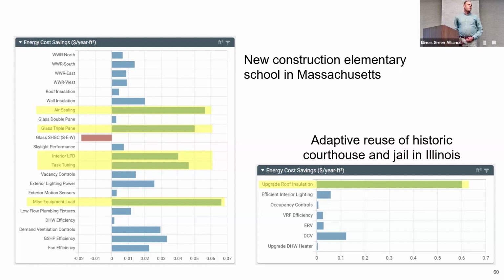What's task tuning? There'll be a high-end trim of the lighting fixtures. So you install, let's say, well these might be T8s, but modern LEDs are all dimmable. You only have so many fixture selections for a space — you've got your ceiling grid, you want to meet 30 foot-candles. Maybe this design has LED fixtures where you can select from 3 different power outputs. You choose the middle one, but your space is still a little bit overlit — maybe you're at 40 foot-candles and you don't really need that much.